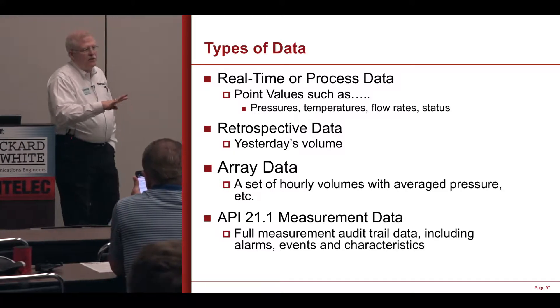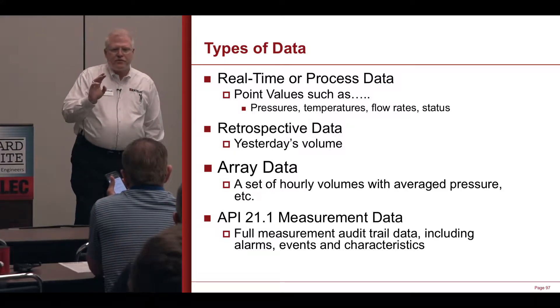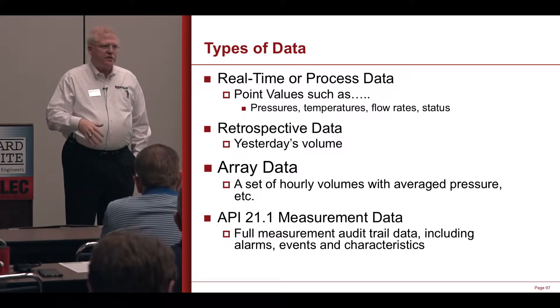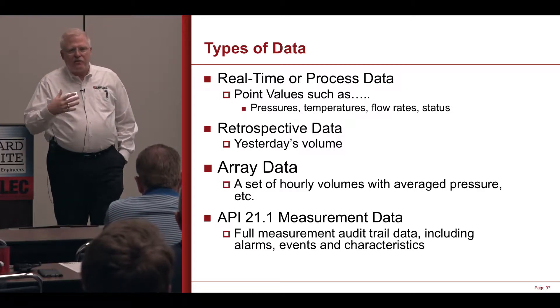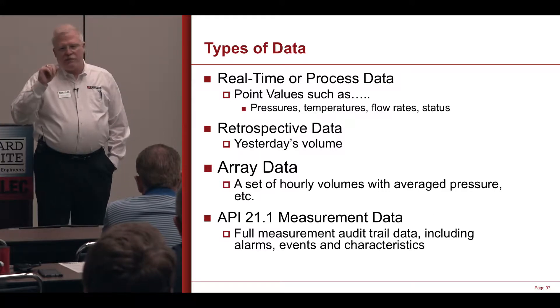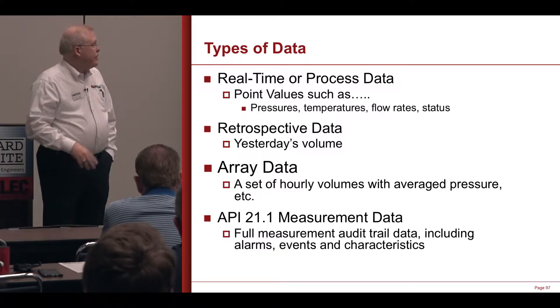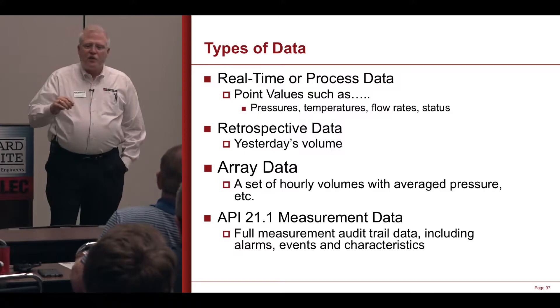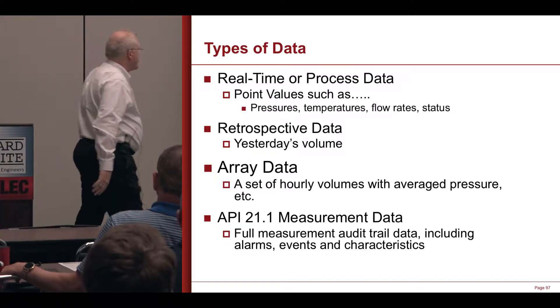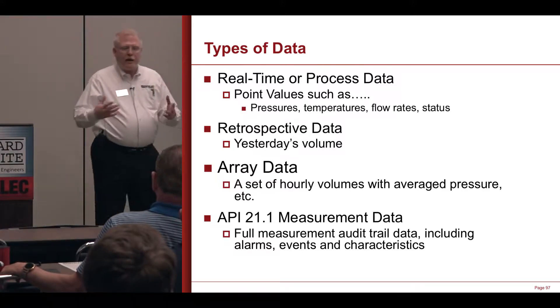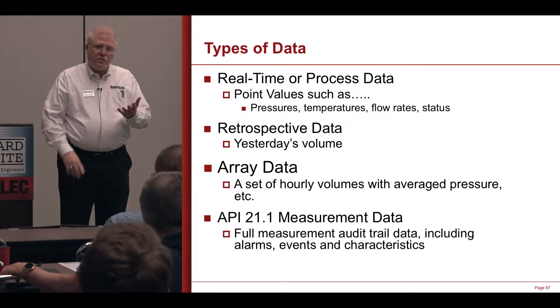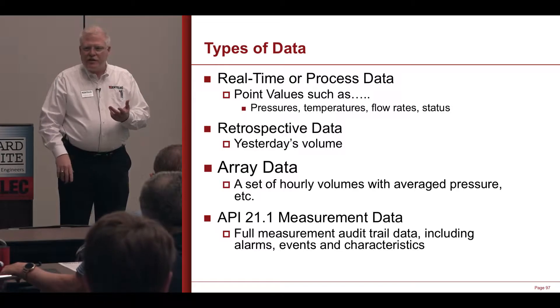In all of this, there are four types of data we focus on. First is real-time or process data — what most SCADA systems primarily focus on: pull the data, bring it up, store it, trend it. Things like current pressure, current flow, current temperature. Second is retrospective data — data that's put together looking backwards, like totalized volume, averaged pressure, average DP. That distinction matters not because it's pulled differently, but because it's handled differently in terms of how it's presented in the HMI.